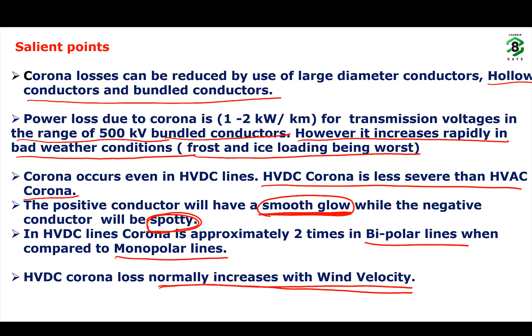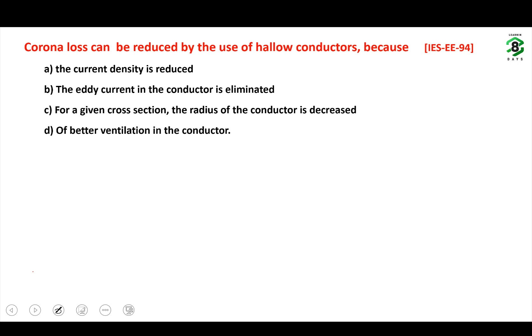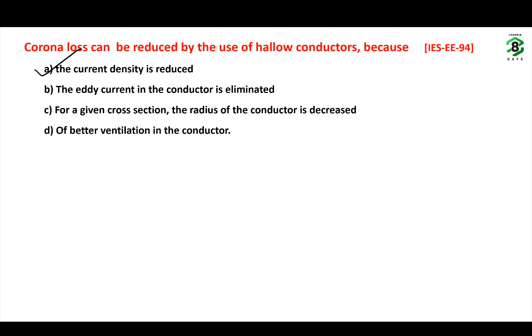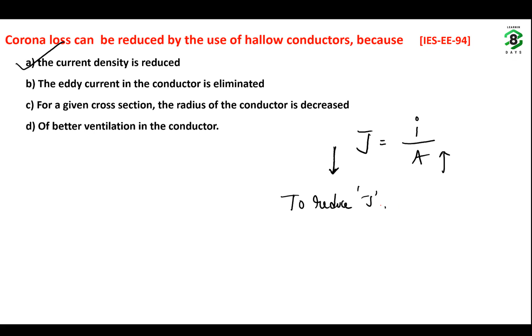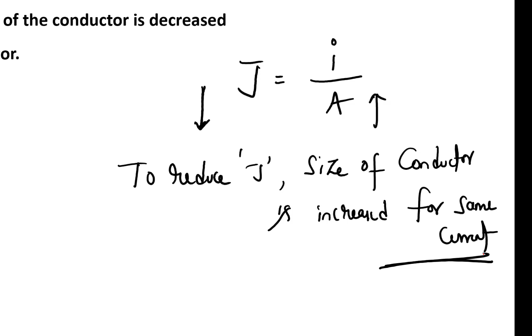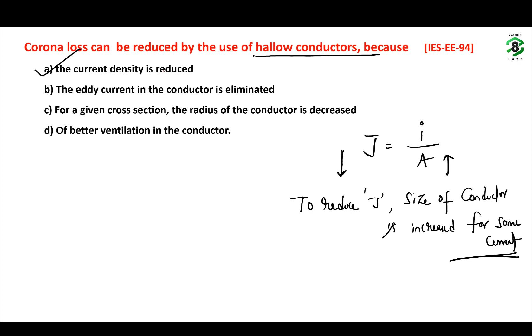Corona loss can be reduced by use of hollow conductors. Why? Because the radius of the hollow conductor is more when compared to the solid conductor. So the current density is reduced. If you remember the formula, current density is the current divided by the area of cross section. To reduce the current density for the same current, we increase the size of the conductor. Once the size of the conductor is increased, the critical disruptive voltage increases and the probability of corona decreases. So in hollow conductors, the current density is reduced, so corona losses are reduced.